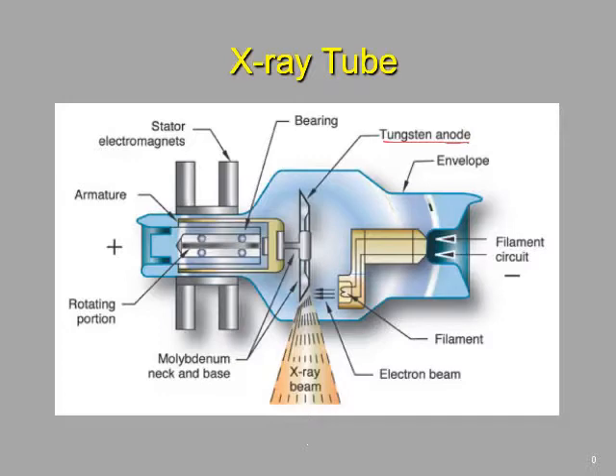The anode is made out of tungsten. Tungsten has a very high melting point and a high Z number, which is helpful because what we're trying to do is give the electrons that we're producing with the cathode something very dense to collide into. That high Z number is helpful because it speaks to how dense the material is.